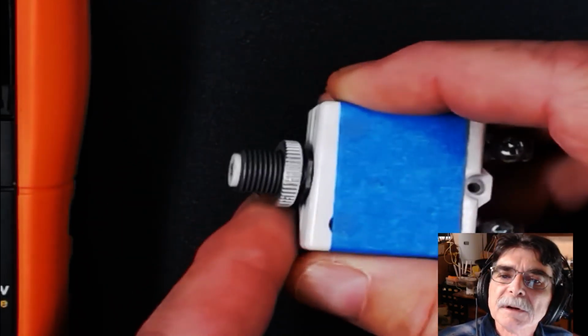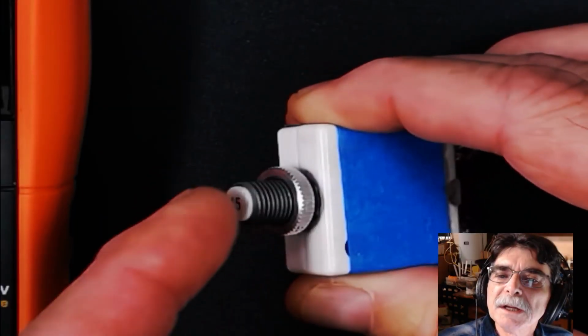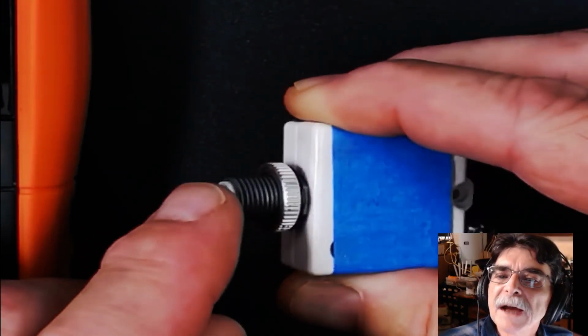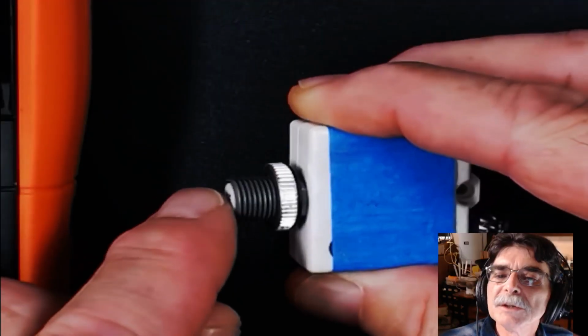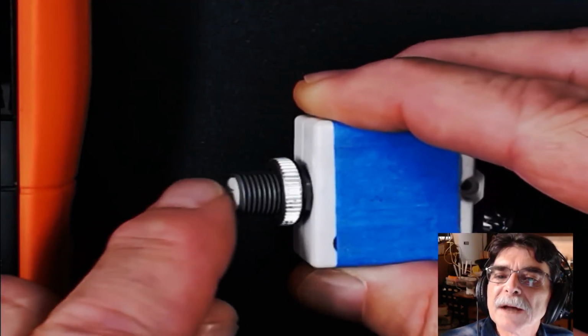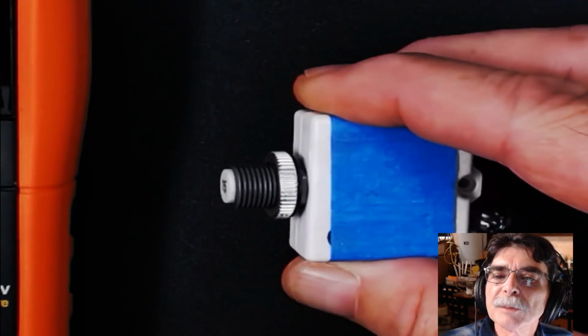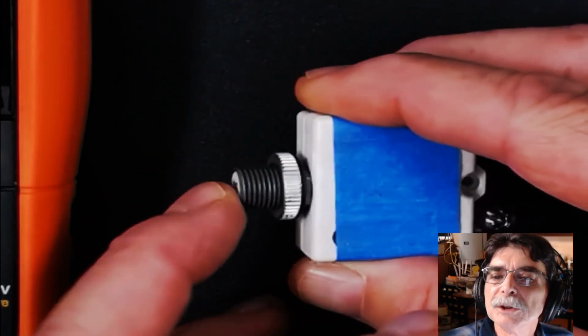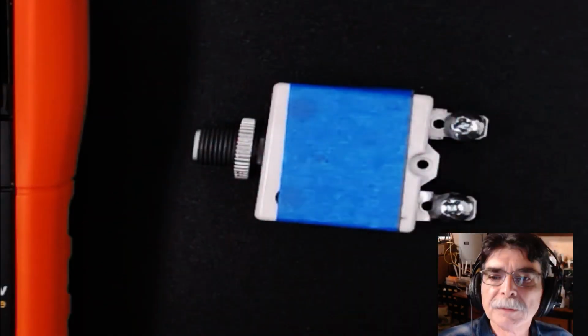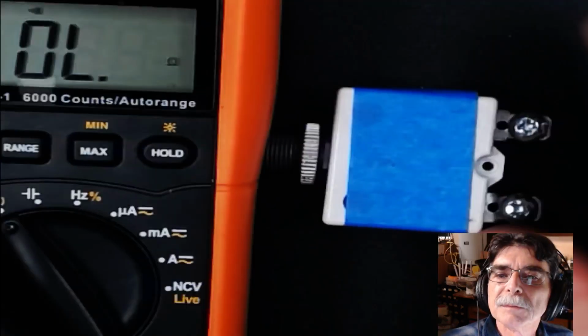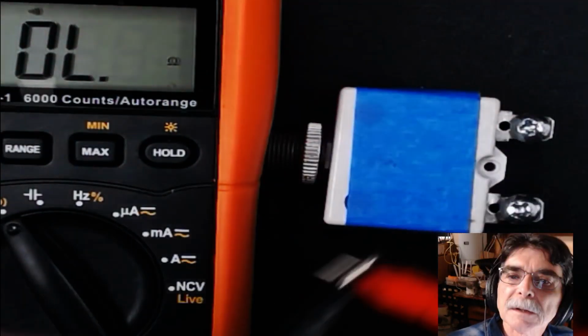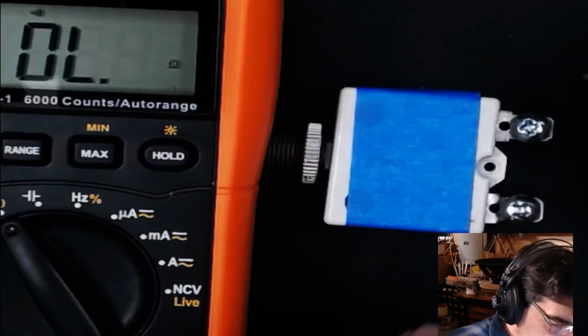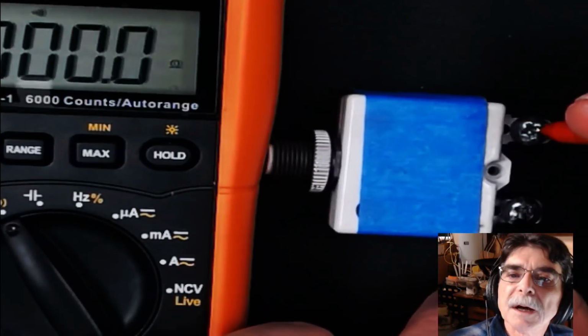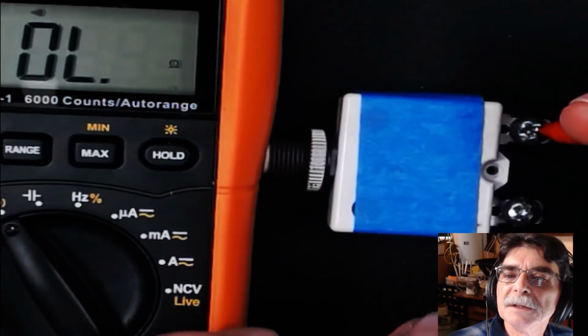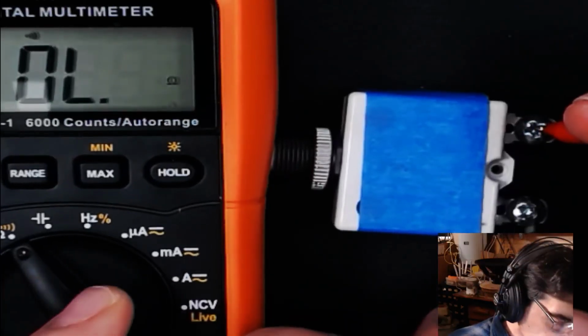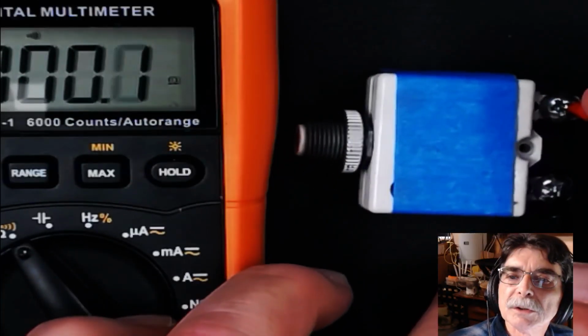We've had folks who say, I push it in and it doesn't do anything. It does actually go in ever so slightly, as you can see, but it's not doing anything. The circuit breaker is still connected, or it's still good. And we can confirm, again, by bringing our meter into play, checking continuity and putting the probes on the circuit breaker, and we see that it is indeed shorted. So this is a good working circuit breaker.